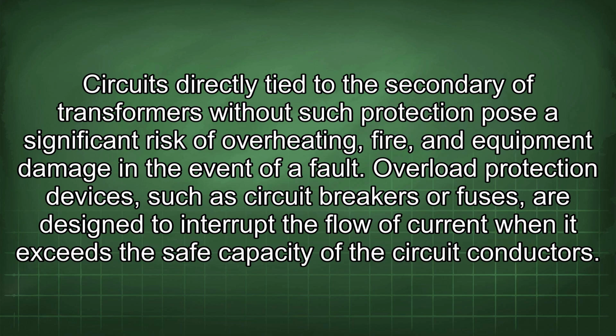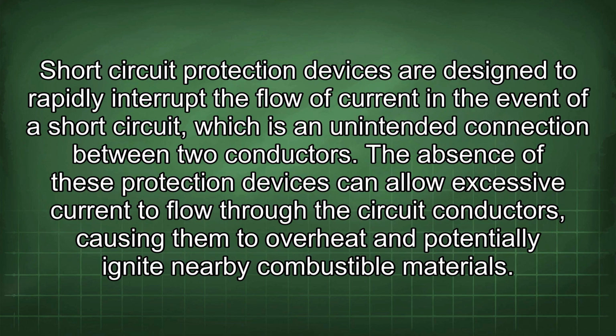Overload protection devices, such as circuit breakers or fuses, are designed to interrupt the flow of current when it exceeds the safe capacity of the circuit conductors. Short-circuit protection devices are designed to rapidly interrupt the flow of current in the event of a short circuit, which is an unintended connection between two conductors.